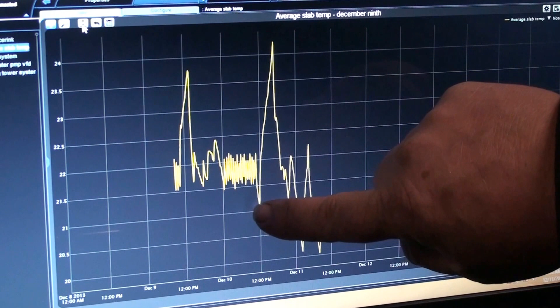And then when the chiller started, and then when it stopped, it was 21.17 degrees. And then when it restarted, this high line right here was 22.03 degrees, down to 20.17 degrees, and then it restarted at 22.23 degrees and shut off at 20.10 degrees. Right at the moment, ice temperature is 20.77 degrees.